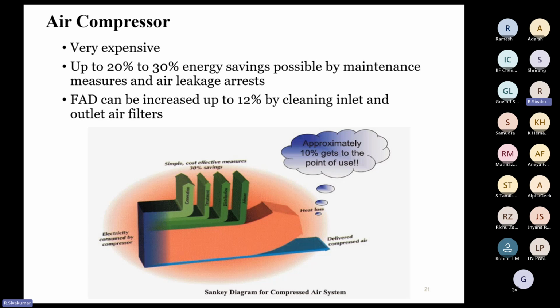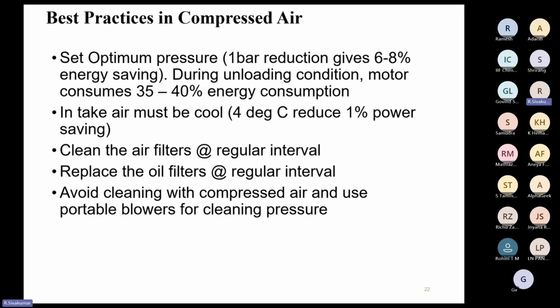Placing the air compressor properly is also very important. Some of the practices: set the optimum pressure. Whatever the capacity of the compressor, whether it's 50 HP, 100 HP or 200 HP, the optimum pressure band is very important. A 1 bar reduction gives straight away 6 to 8% energy saving.